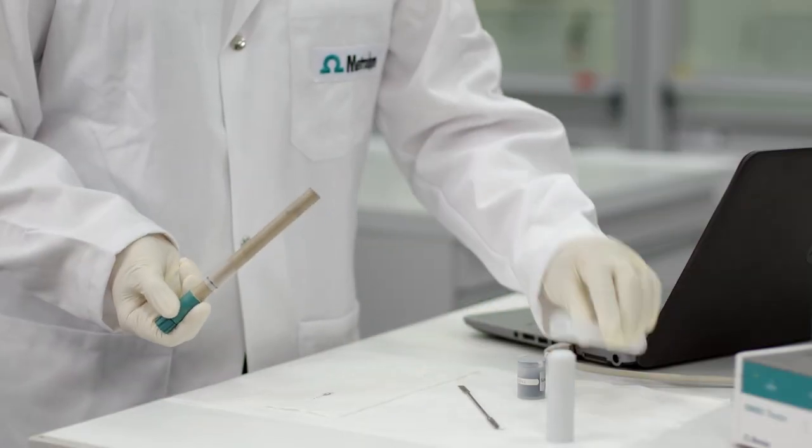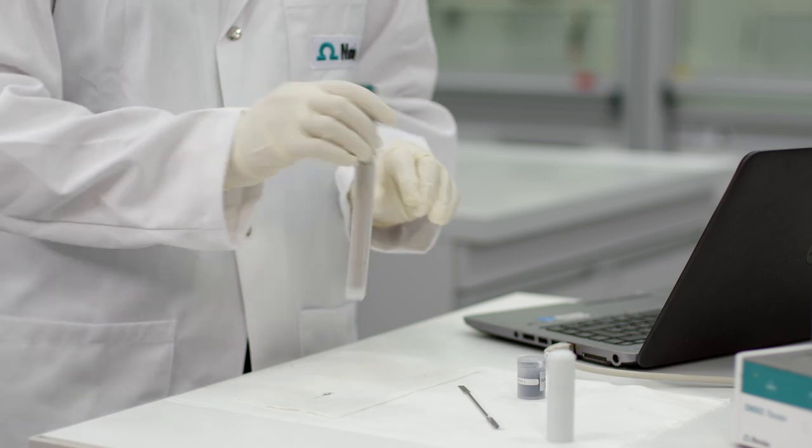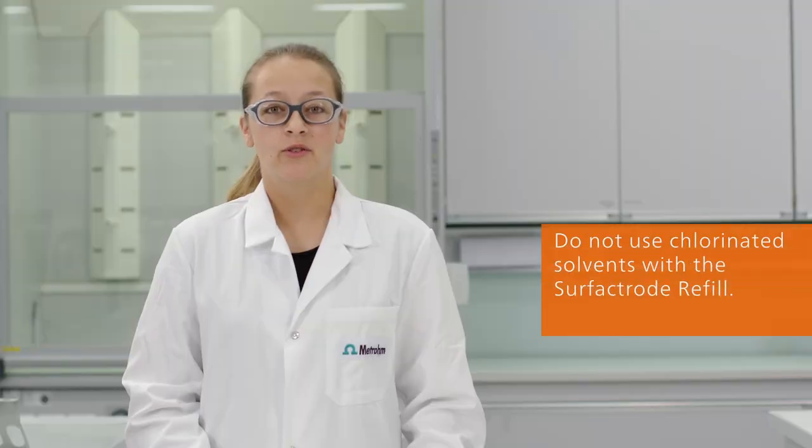Finally, don't forget to store the electrode dry after a series of titrations. Be aware that the Surfactrode Refill is not resistant to chlorinated solvents.